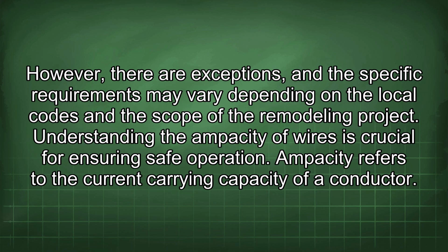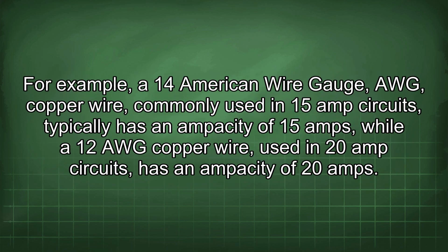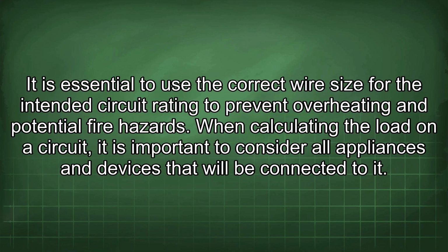Ampacity refers to the current carrying capacity of a conductor. For example, a 14 American wire gauge (AWG) copper wire, commonly used in 15-amp circuits, typically has an ampacity of 15 amps, while a 12 AWG copper wire, used in 20-amp circuits, has an ampacity of 20 amps. It is essential to use the correct wire size for the intended circuit rating to prevent overheating and potential fire hazards.